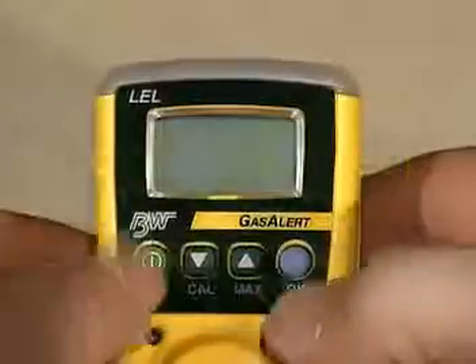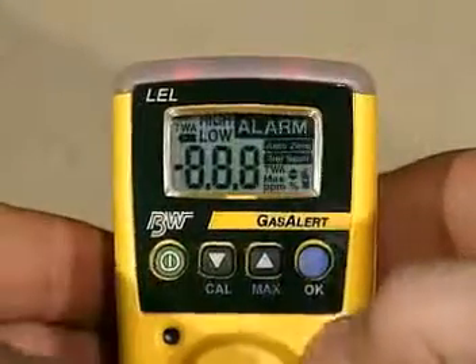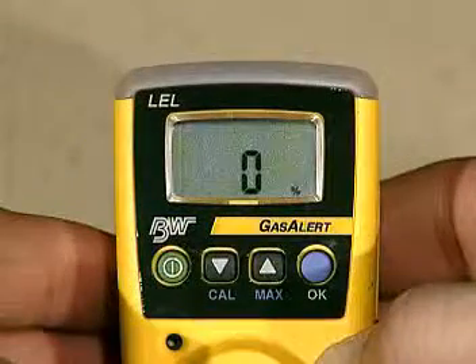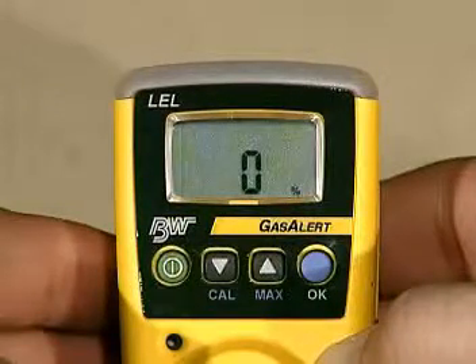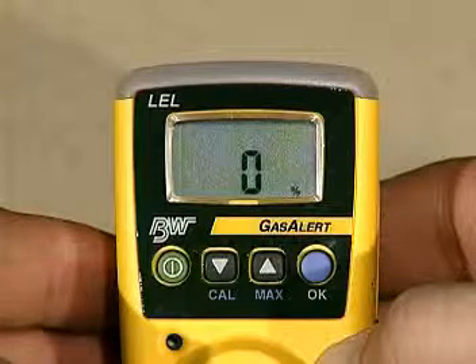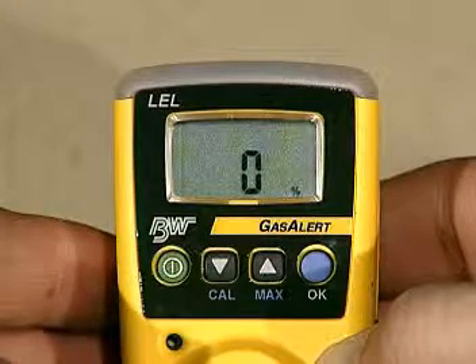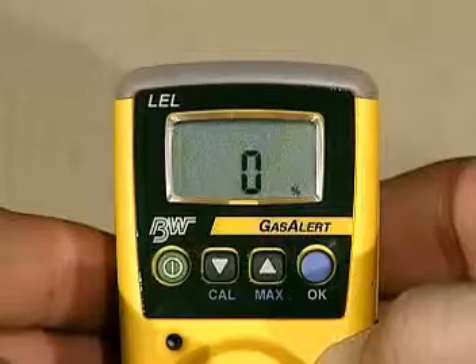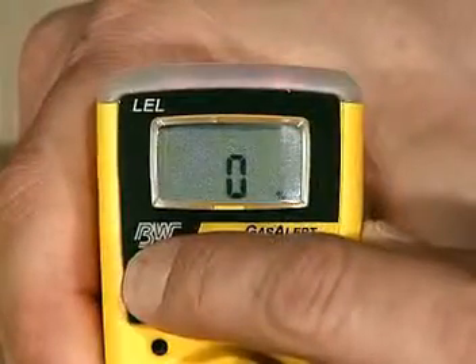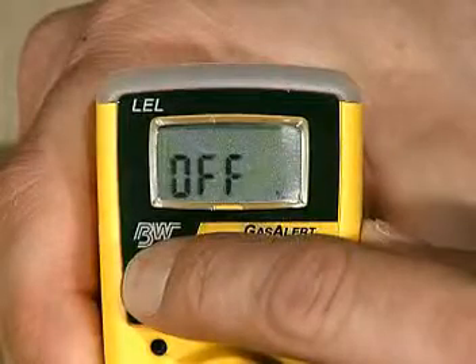To activate the confidence beep, press the green and OK buttons together at startup. The confidence beep tells you that the instrument is on and working. Instead of beeping when the battery is low, the detector beeps to advise that the battery has sufficient power and stops beeping when the battery is low. To deactivate the confidence beep, turn off and then restart the detector.